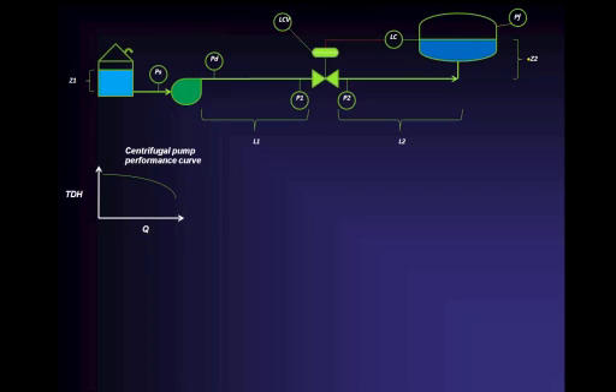We've got a little graph there called the centrifugal pump performance curve. On the y-axis, we have TDH. That's a pump curve that would be called the total developed head, or total dynamic head, some people call it. It's measured in feet of liquid pumped. The x-axis is Q, the flow rate that the pump delivers. Every centrifugal pump has essentially a characteristic that provides for decreasing pressure that we can pump against with a need for increasing flow. The more flow we've got to get through the pump, the less pressure it can do that against, and that's where you see the droop in that green curve.